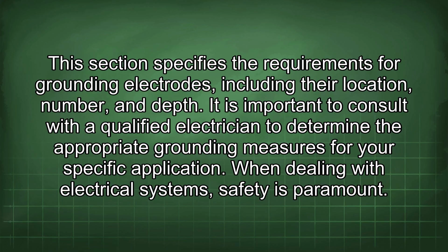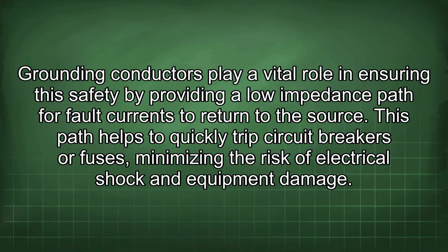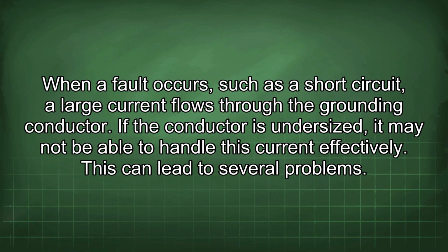When dealing with electrical systems, safety is paramount. Grounding conductors play a vital role in ensuring this safety by providing a low impedance path for fault currents to return to the source. This path helps to quickly trip circuit breakers or fuses, minimizing the risk of electrical shock and equipment damage. When a fault occurs, such as a short circuit, a large current flows through the grounding conductor. If the conductor is undersized, it may not be able to handle this current effectively. This can lead to several problems.